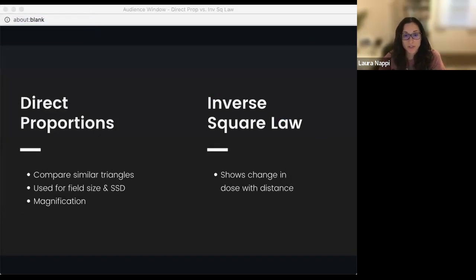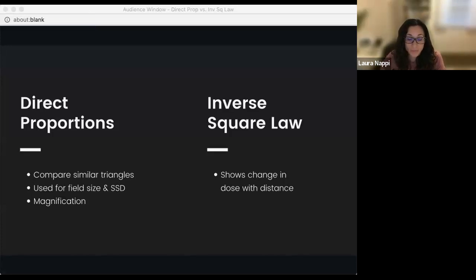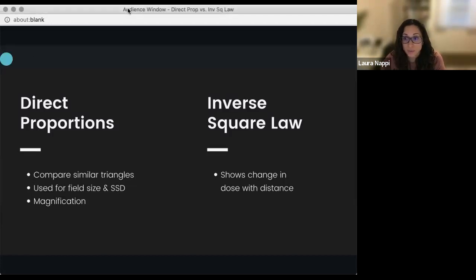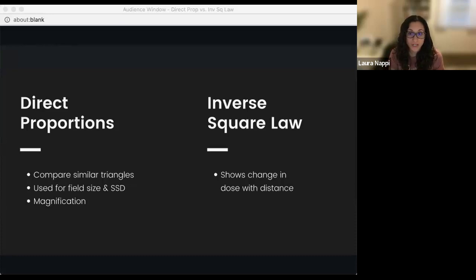We will mainly use direct proportions when we're trying to find new field sizes at different distances or SSDs. The beam is naturally in the shape of a triangle — as SSD increases or as the distance increases, the width of the triangle increases in proportion to that distance, so divergence is predictable. Whenever we're talking about field size and distance, we will use a direct proportion. A common analogy is the flashlight: as you shine it against a wall and pull it further away, the circle gets bigger.